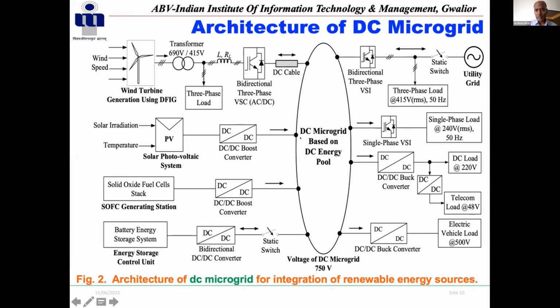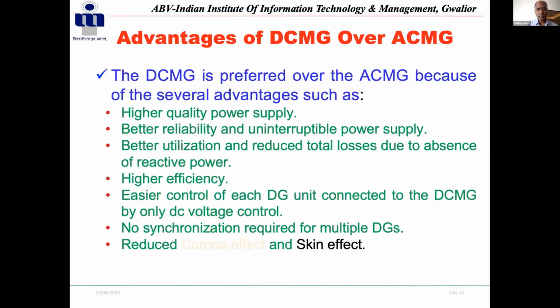We connect PV directly to DC, using boost converters to reach the chosen voltage level, say 750 volts. Fuel cells and batteries are also DC, while loads may be AC or DC. If you need AC interconnection, you require voltage source inverters for DC to AC conversion. Various DC and AC loads can be connected through converters and inverters, and this completes the architecture of the DC microgrid.